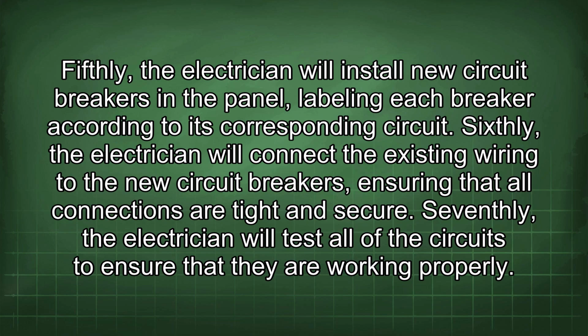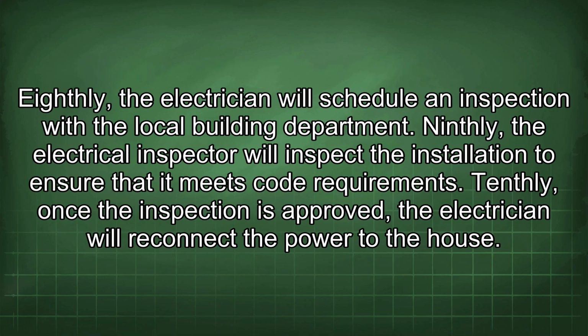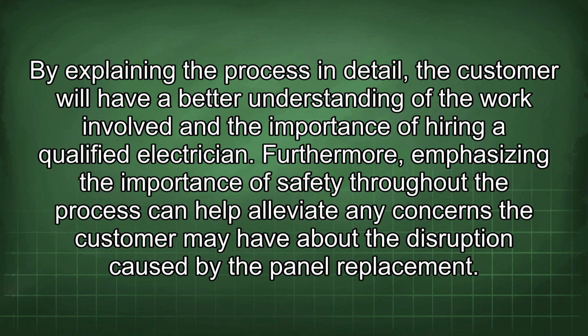Sixthly, the electrician will connect the existing wiring to the new circuit breakers, ensuring that all connections are tight and secure. Seventhly, the electrician will test all of the circuits to ensure that they are working properly. Eighthly, the electrician will schedule an inspection with the local building department. Ninthly, the electrical inspector will inspect the installation to ensure that it meets code requirements. Tenthly, once the inspection is approved, the electrician will reconnect the power to the house. By explaining the process in detail, the customer will have a better understanding of the work involved and the importance of hiring a qualified electrician.